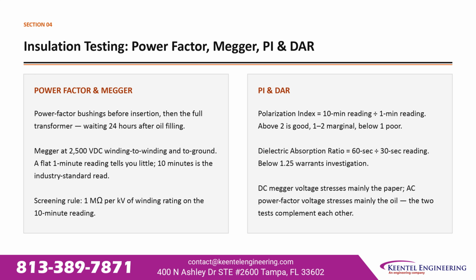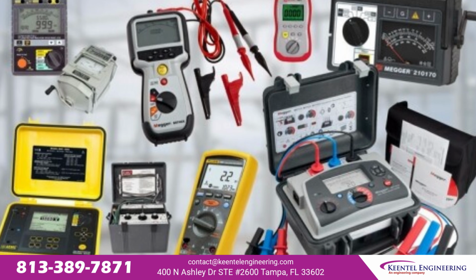Megger at 2,500 volts DC, winding to winding and winding to ground. A flat 1-minute reading tells you very little. 10 minutes is the industry standard read. The screening rule is 1 megohm per kilovolt of winding rating on that 10-minute reading. 2 ratios matter here. Polarization index is the 10-minute reading divided by the 1-minute reading. Above 2 is good, 1 to 2 is marginal, below 1 is poor. Dielectric absorption ratio is the 60-second reading divided by the 30-second reading. Below 1.25 warrants investigation. Worth remembering, DC Megger voltage mainly stresses the paper insulation, while AC power factor voltage mainly stresses the oil. The 2 tests complement each other.